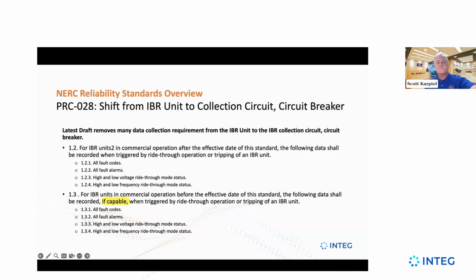But we are seeing complete sites being repowered because some of the manufacturers that were around 10 years ago aren't around today. Oh, geez. They can't get replacement parts. They can't get maintenance. There's no maintenance out there. So they're going through what we call repowering in the industry. Once they do that, if it's after the effective date, they need to make sure that the new equipment, whether it's the inverter, the collection circuit breaker, or a relay up at the MPT, doesn't matter, once you replace that piece of equipment, it has to meet the new requirements. And I believe that's the same way with PRC 29, and PRC 28 will depend on your agreement, the LGIA.